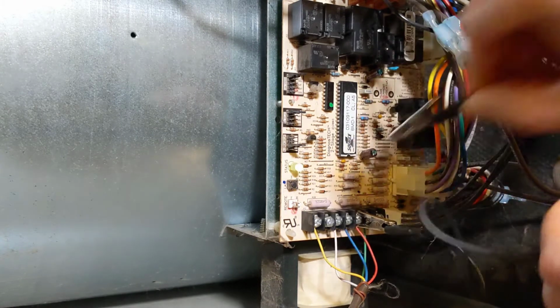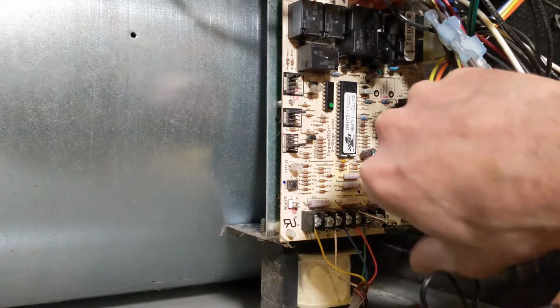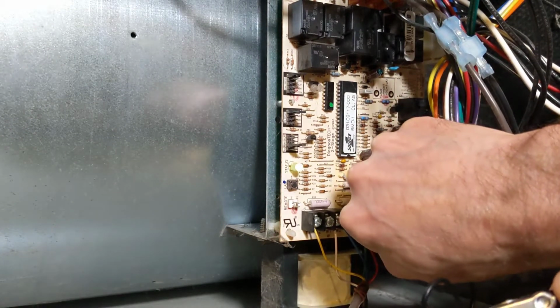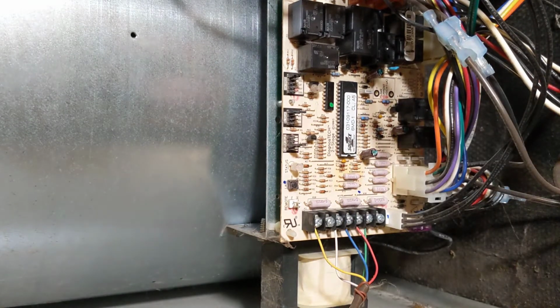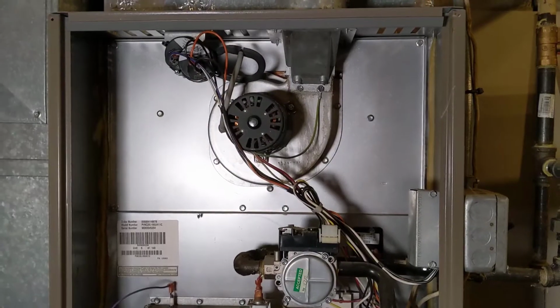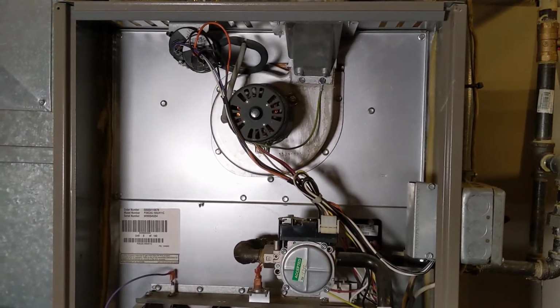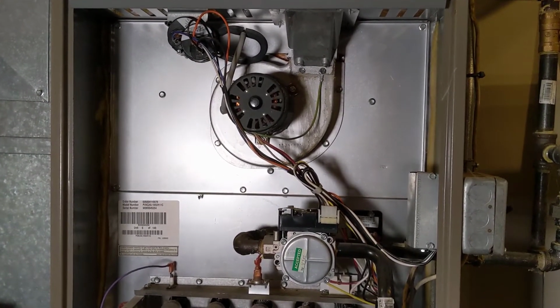And you can see, I'm going to turn it off now, you can hear that the inducer fan starts coming on. So we know that the problem is our thermostat is not properly making that connection, and we can go to Home Depot and buy a replacement thermostat or replace the batteries in it, and that should take care of our problem.